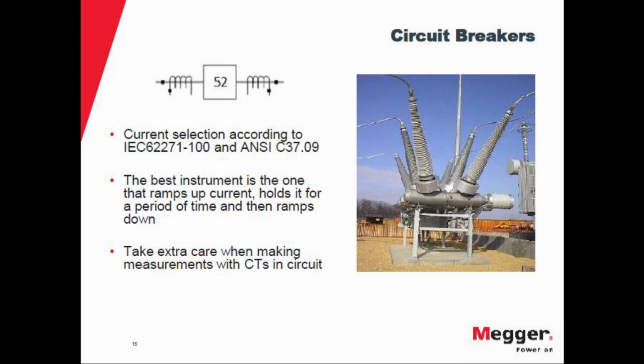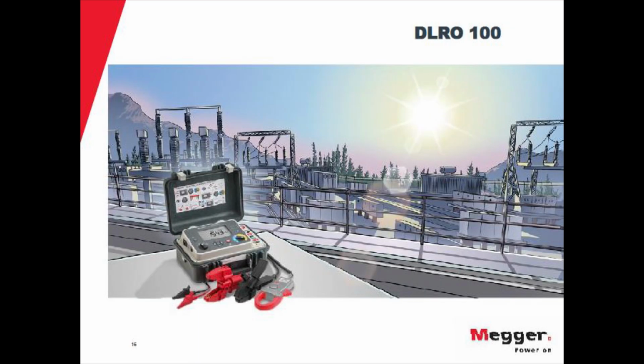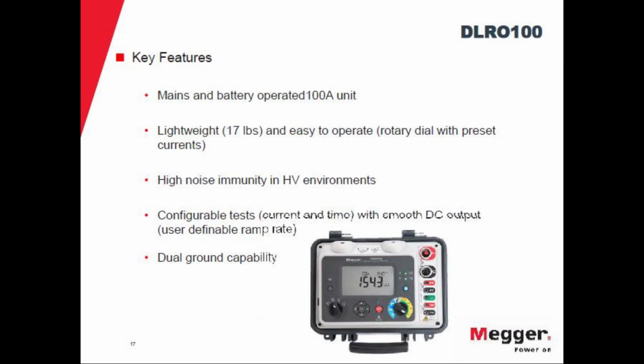So you can't use just any low resistance measurement instrument. You have to use something that has a very good signal and can handle the ramp of the current that you are injecting. So what we have for this purpose is the DLRO 100. It's a unit that can inject 100 amps. You can run the test with any current that you want, depending on what you are testing. Basically, the concept you have to follow to select the current for the test is never to exceed the nominal current of what you are testing.